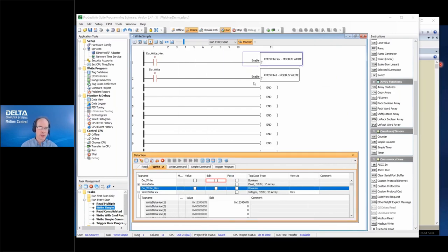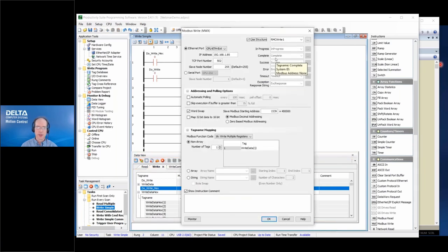We'll go try a regular write here. We'll see what that is. We're writing to 1539, so that's variable 1. Remember, we were at 1537, and because it's a 16-bit protocol, we have to increment by 2 to write to the next 32-bit data, and that's writing from write data 1 as well.